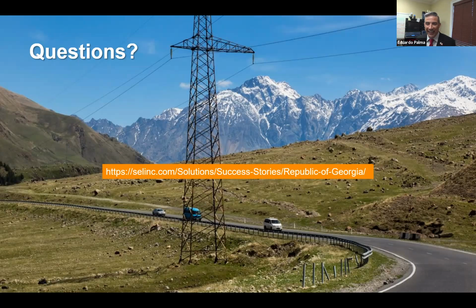controllable. And also the short circuit studies are going to be different when those intermittent generation stations are not available because there's no sun or there is no wind. So when they're not available, not because of a fault, just because of the weather, then we also have to compensate and do a lot of coordination. And this takes engineering, which we're good at, so we can take care of that.